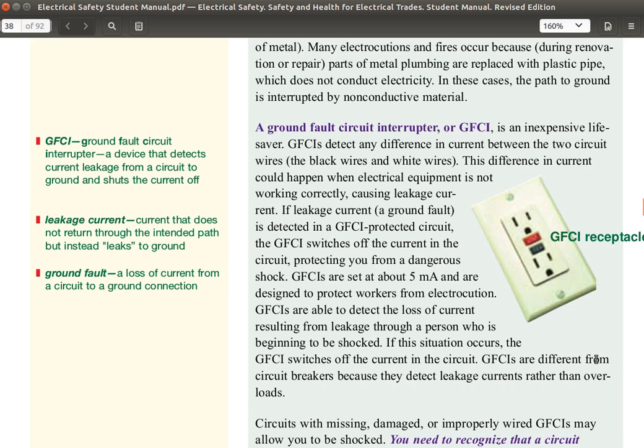GFCIs are different from circuit breakers because they detect leakage current rather than overloads. Nowadays, you do have some circuit breakers that are GFCI circuit breakers, but they are also designed to trip on overload, so they have both features. If you have a GFCI plug, it should be accompanied by a GFCI circuit breaker.